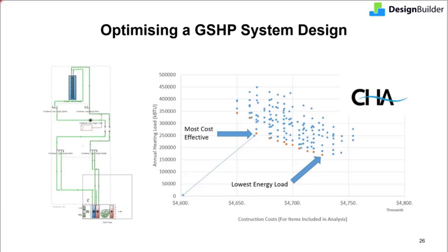The project, completed by Karpinski Engineering, focused on optimizing the balance between heating and cooling loads in a ground source heat pump system. This is because heat pumps provide both heating and cooling, and if sized optimally, they can save significantly on plant costs. This becomes more important in ground coupled systems where heat rejection to and from the bore field has a big impact on the size and cost of the ground loop.